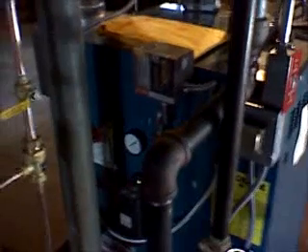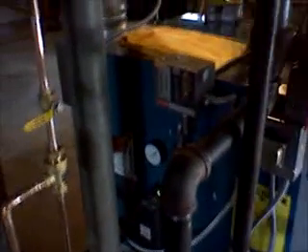So when you deal with steam systems, venting is everything. You don't want pressure on these small residential systems. Pressure is not needed at all. Basically, the way you think about it is that when a steam system is off, all the pipes are full of air. When you boil the water to make the steam, you have to displace the air that is inside the pipes. And so when the steam boils, it rises up and displaces the air through the air vents.